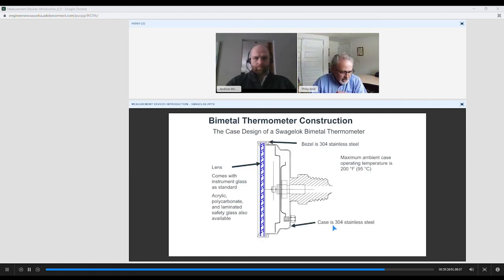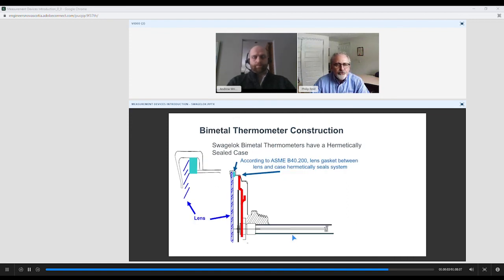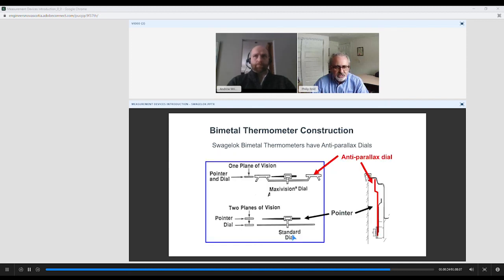Okay, so now I wanted to take a closer look at the lens area of that gauge. This bimetal case has the bezel. It is sealed so that this lens, which can be instrument glass or acrylic, doesn't get fogged up. There's nothing worse than trying to read a fogged up gauge or thermometer. The maximum ambient conditions for this case are 200 degrees Fahrenheit or 95 C. And again, it's all stainless steel construction. In accordance with ASME B40.200, lens and gaskets are hermetically sealed, as we talked about. This is something that happens in thermometers a lot. They lose a seal. Not these thermometers as much as some of the lower grade thermometers that don't use the same technology.